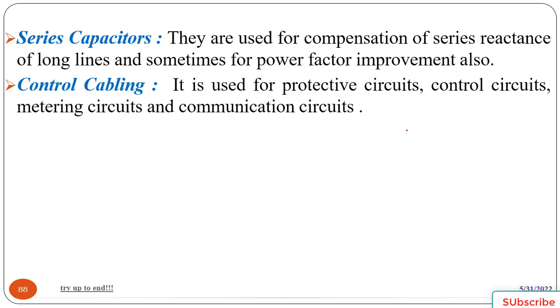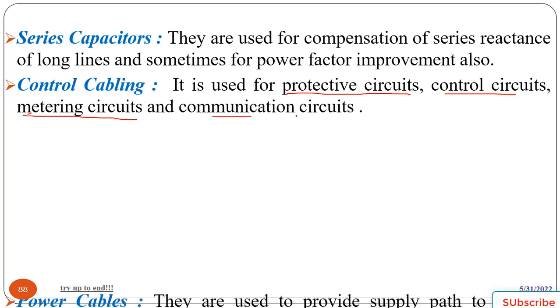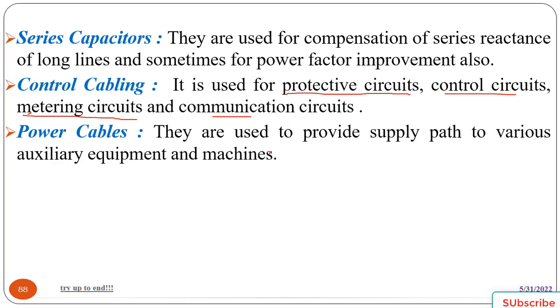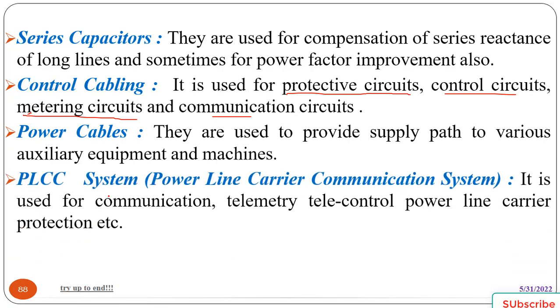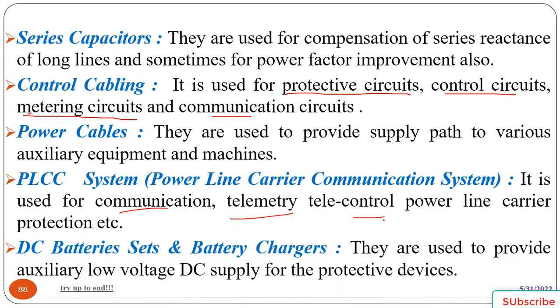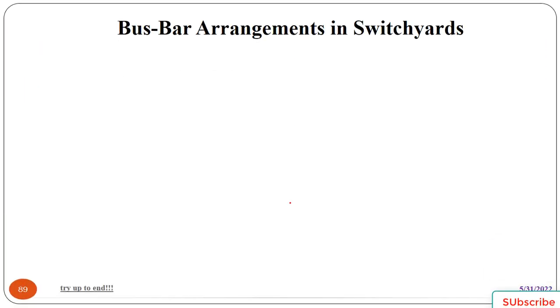Control cabling is used for protection circuits, control circuits, metering circuits and communication circuits. It incorporates protective circuits, control circuits, metering and measuring circuits, and communication circuits that give information. Then there are power cables, which are used to provide supply to various auxiliary equipment and machines. The power line carrier communication system is used for communication, telemetry, telecontrol and protection. Then there are DC battery sets and battery chargers. They are used to provide auxiliary DC voltage supply for protective devices.